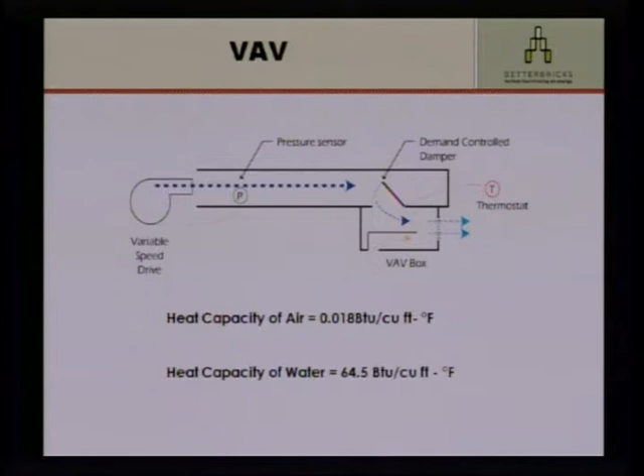Air doesn't hold energy, so you have to use a huge amount of it to move any amount of energy at all. It's also compressible, which means when a fan starts spinning, the air doesn't start moving right away—it has to build momentum and compress. Whereas with a liquid like water, the minute the pump spins, full volume is going, because water isn't compressible.